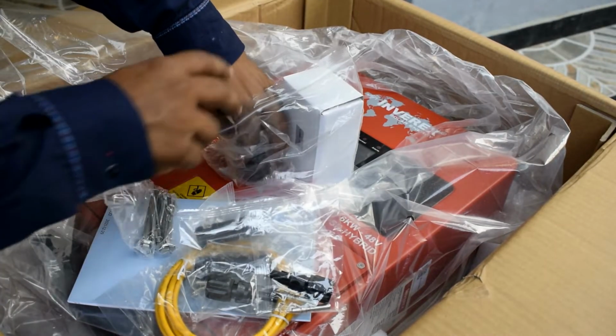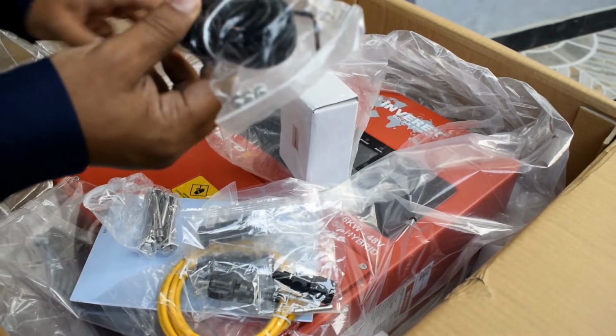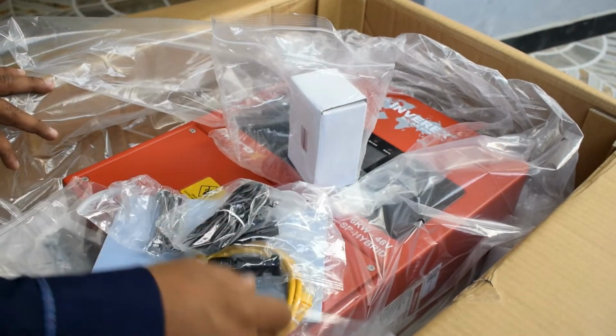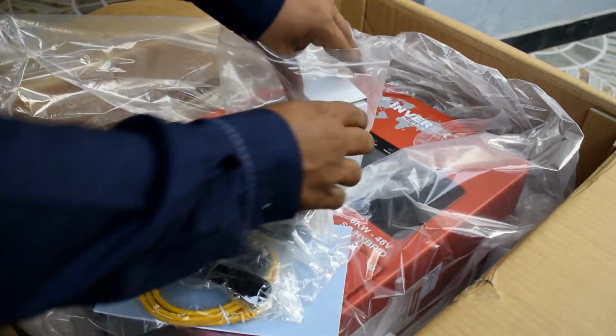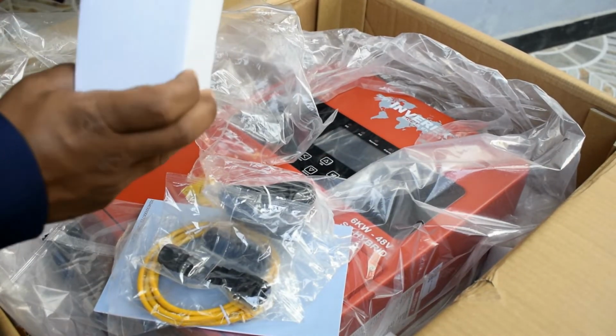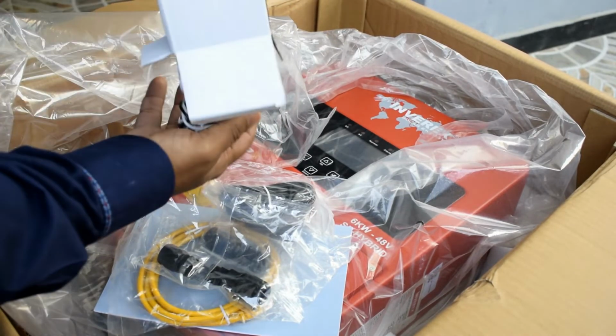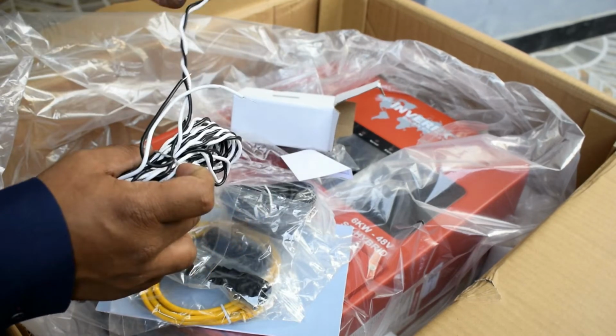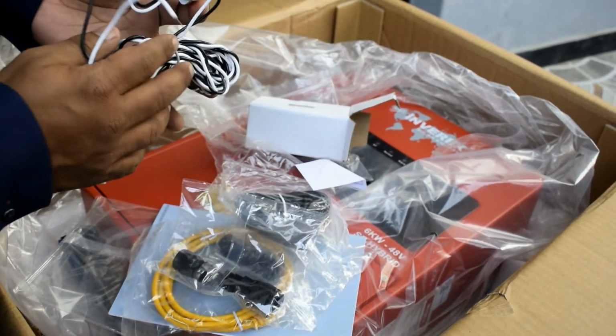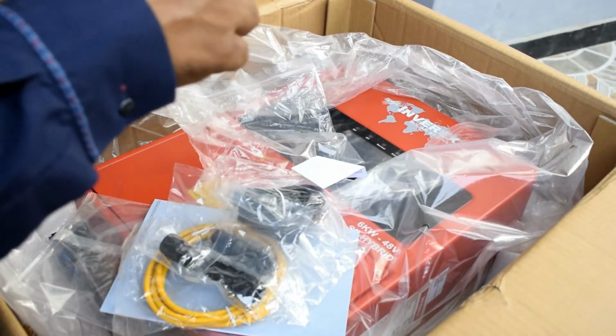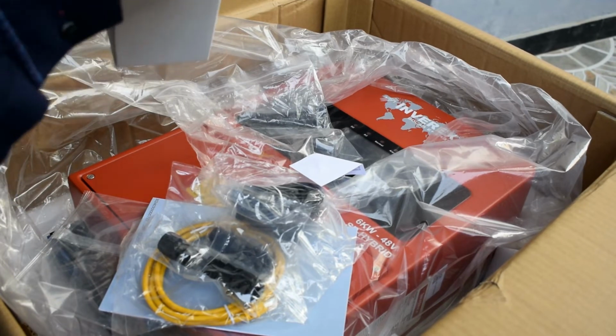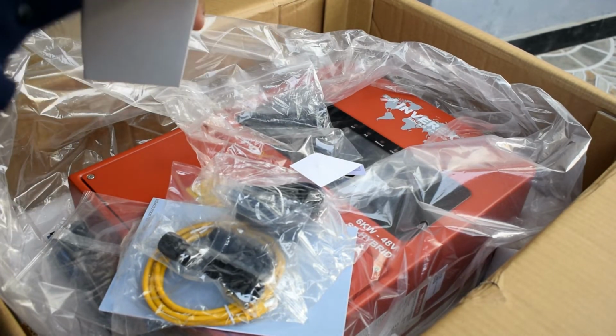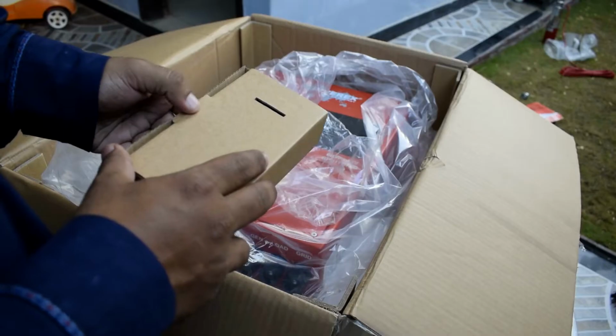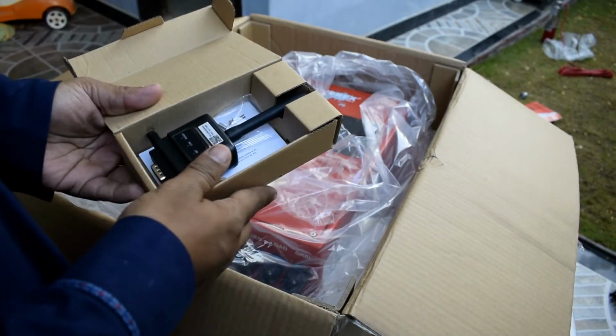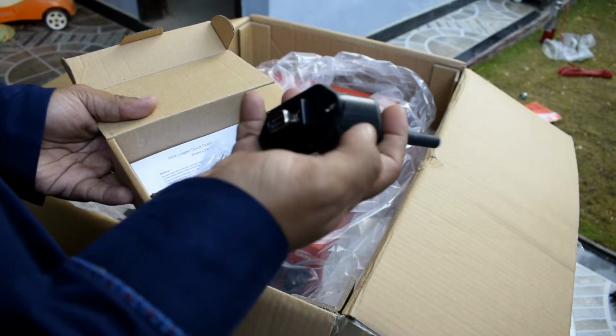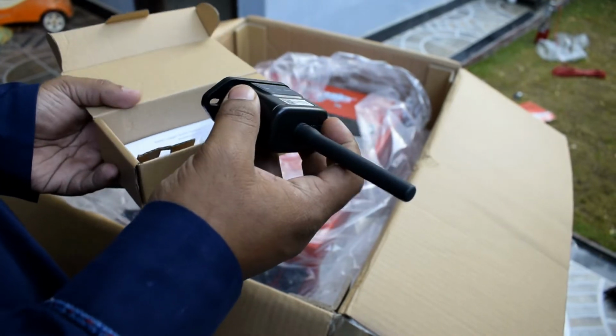These are the anchor bolts, and this is the communication cable for reverse metering, if we can. Okay, so these are the accessories, and in this box we have a CT for measuring the current. With this CT we can calculate how much power we are consuming from K Electric and from the solar, so we can do a comparative analysis. The last accessory is its Wi-Fi module. You connect this Wi-Fi module so the inverter can connect to the internet, and you can access its statistics anywhere else.